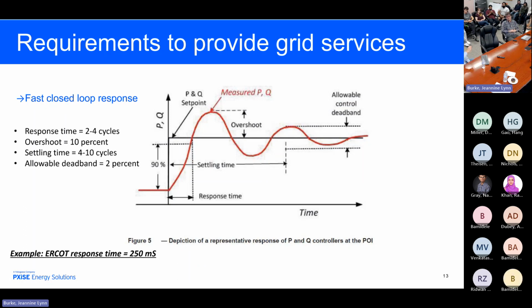Now, most people in the power industry are not used to feedback control systems. They're used to open loop control, droop control, for example. Oh, when the frequency gets to this, I go to that. Okay, that is some form of feedback, proportional feedback. But in our opinion, the feedback control system that is needed to achieve this kind of response is at least a PID type of controller. You need the integral to get to 0, set point. You need the derivative to get you there fast and slow you down as you approach the set point. And you need the proportional to figure out how much you're going to need.